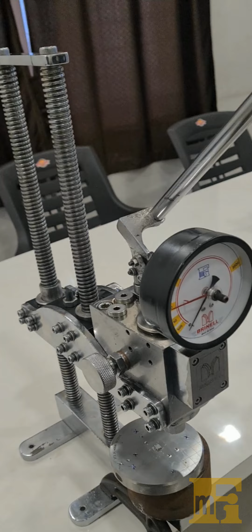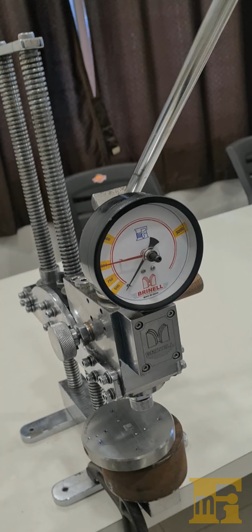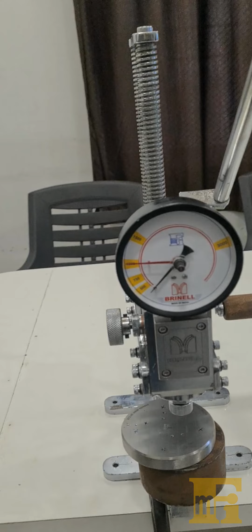Perform Brinell hardness test. The uniqueness of this machine is that it can apply any two selected Brinell test forces. This particular machine is currently set up for 1000 kg load and 3000 kg load. So this machine can perform 3000 kg load with a 10 mm ball for steel material, and 1000 kg load with a 10 mm ball or 1000 kg load with a 5 mm ball for non-ferrous materials such as aluminum, brass, etc.